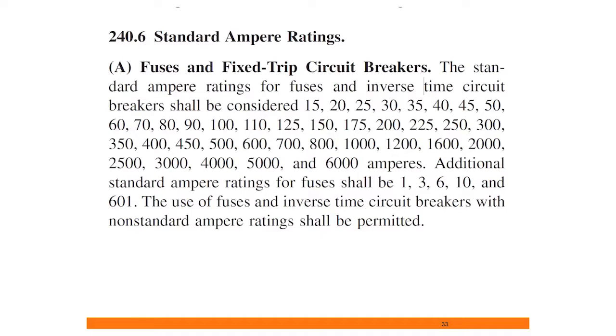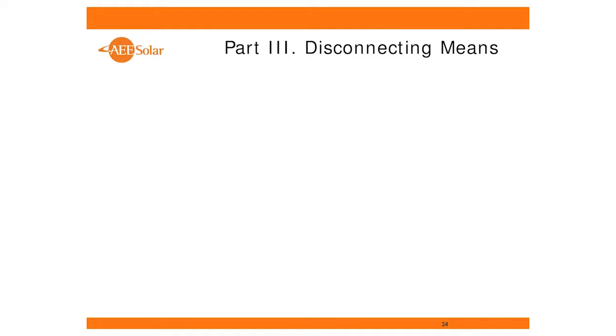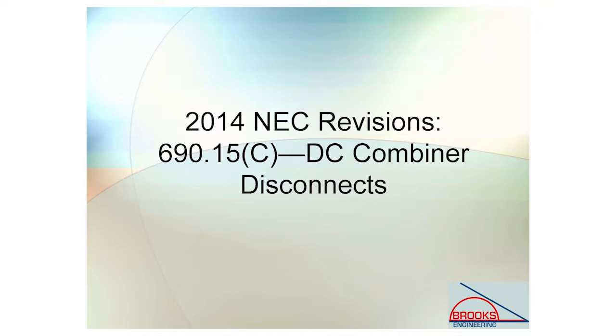All right, so here's your standard ampere ratings. I always like to, I love this one. There's a standard ampere rating of 601 versus 600. Did you know that? Somebody got their little rating in there. Has to do with kVA of a transformer and stuff like that, but anyway. Is there a difference between a 600 and a 601 overcurrent device? Other than the 1 on it, there is absolutely no difference whatsoever. Because the accuracy of those devices ain't anywhere close to the 3rd decimal place, not even close.